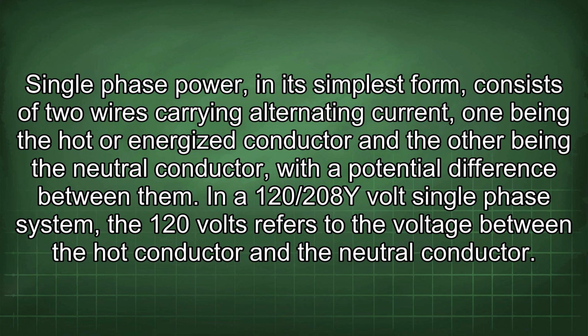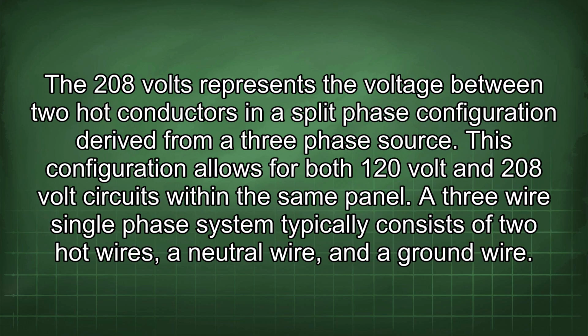Single-phase power, in its simplest form, consists of 2 wires carrying alternating current, one being the hot or energized conductor and the other being the neutral conductor, with a potential difference between them. In a 120/208 volt single-phase system, the 120 volts refers to the voltage between the hot conductor and the neutral conductor. The 208 volts represents the voltage between 2 hot conductors in a split-phase configuration derived from a 3-phase source. This configuration allows for both 120 volt and 208 volt circuits within the same panel.